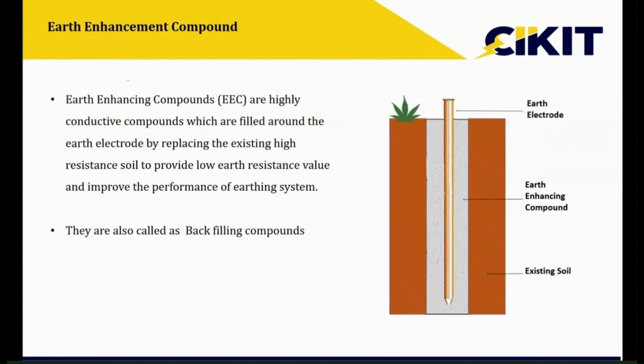So many people will be considering that we are replacing the soil with the compounds only for achieving lower resistance. That is not the actual case. If I'm working with very low soil resistivity conditions, where the corrosion rate will be more, then in order to protect the earth electrode from the corrosion, this compound comes into the picture.